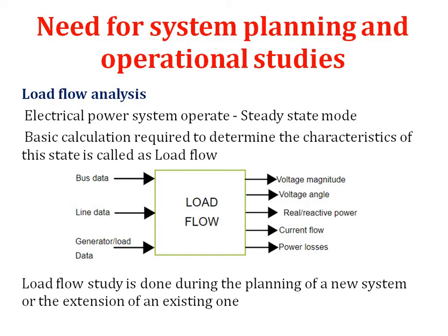Load flow analysis. The electrical power system operates in steady state mode. The basic calculation required to determine the characteristics of this state is called load flow. The input side has the schematic diagram, bus data, line data, generator or load data. The output side has voltage magnitude, voltage angle, real and reactive power flow, current flow, power loss. Load flow studies are done during the planning of a new system or for the extension of an existing one.